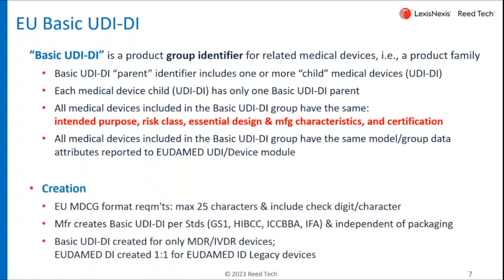How do you go about creating this? The burden is on the actual manufacturer to create the Basic UDI-DI. Each of the standards — GS1, HIBCC, ICCBBA, and IFA — I know it's an alphabet soup — but each of those issuing entities have guidelines on how you create this particular value.